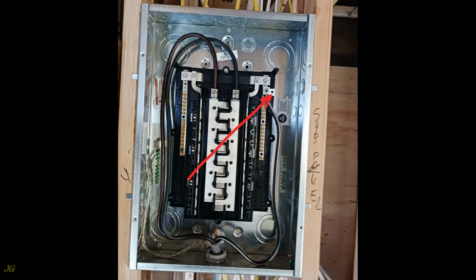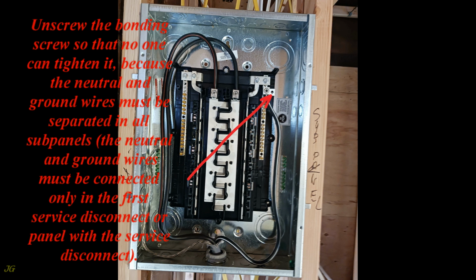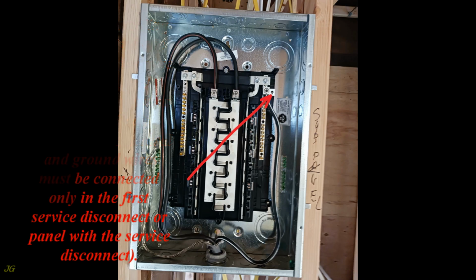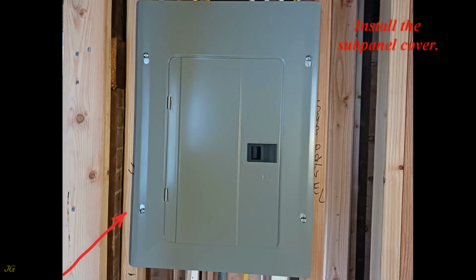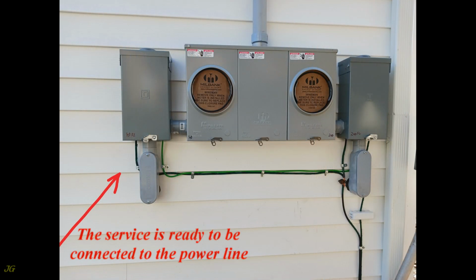Unscrew the bonding screw so that no one can tighten it. Because the neutral and ground wires must be separated in all subpanels, the neutral and ground wires must be connected only in the first service disconnect or panel with the service disconnect. Install the subpanel cover. The service is ready to be connected to the power line.